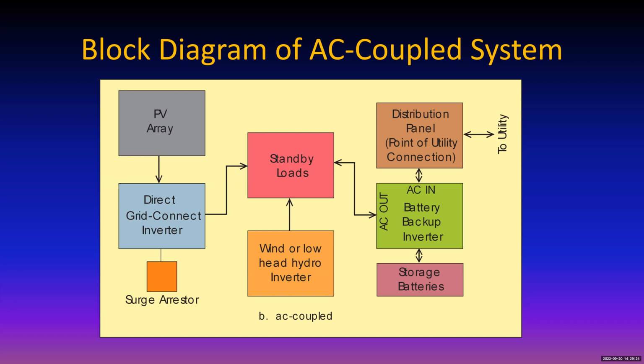When the utility goes down, the green inverter has to make a utility quality sine wave, which finds its way up to the standby load panel. The direct grid connect inverter sees that, which tells it that it's okay to make electricity by converting the solar DC into AC. That's all well and good, but at night the story changes.